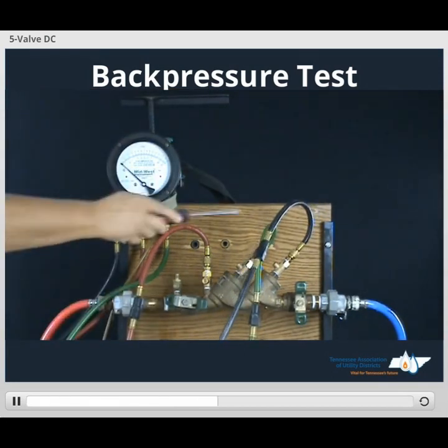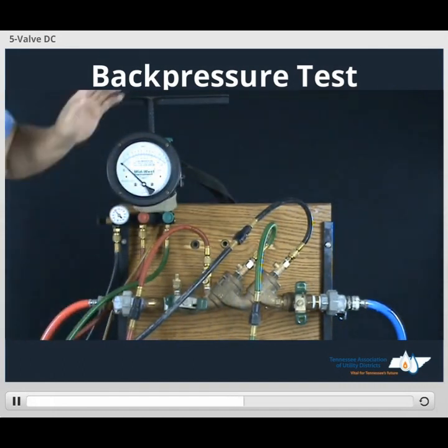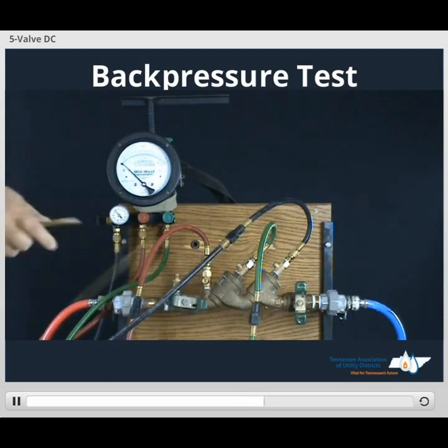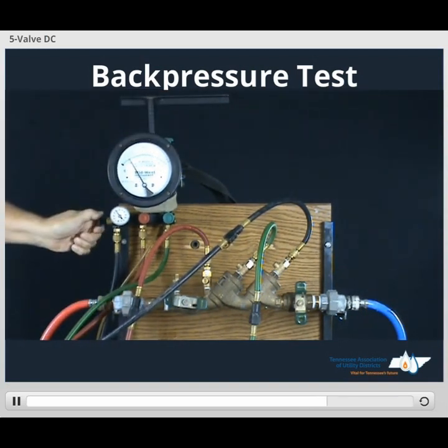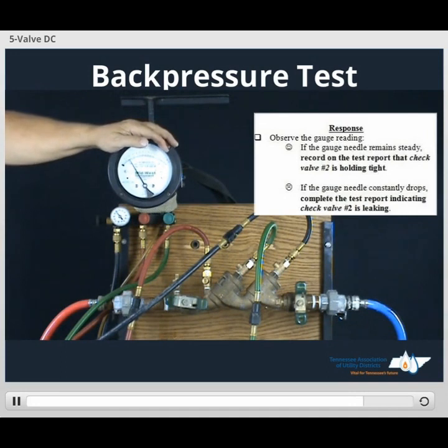Take our screwdriver, open test cock number 4. We've got to reset our gauge, so we'll secure our bleed hose, open up our low side bleed. Once the gauge reaches the different scale, close low side bleed — this has our gauge ready. Now when we open up our bypass valve, we will apply back pressure against check valve number 2. Our gauge remains steady and does not drop to zero — it means check valve number 2 is holding tight against back pressure.